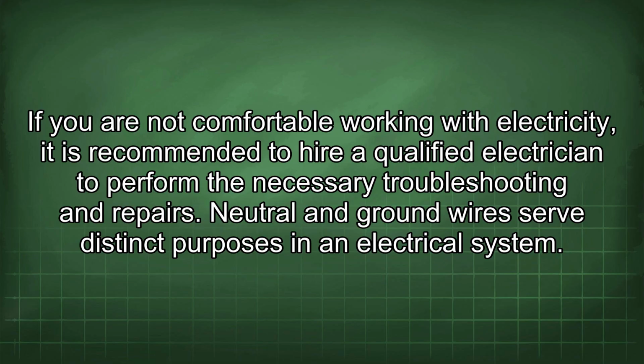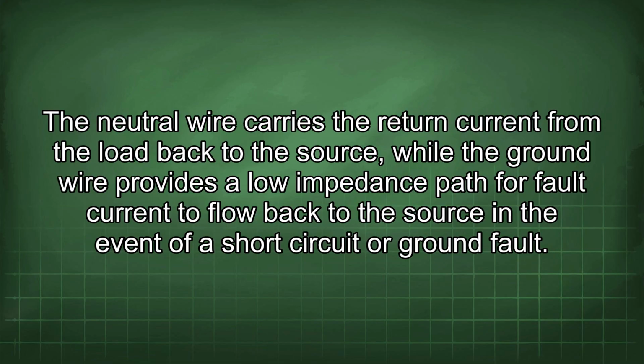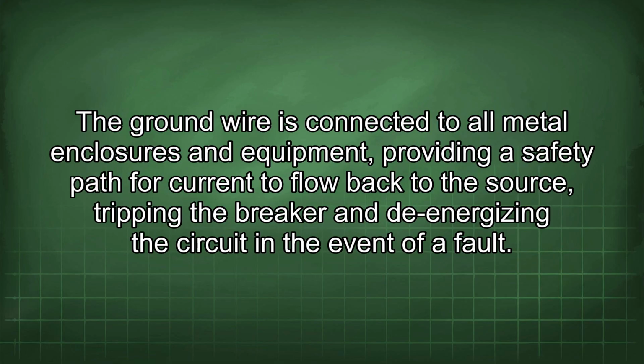If you are not comfortable working with electricity, it is recommended to hire a qualified electrician to perform the necessary troubleshooting and repairs. Neutral and ground wires serve distinct purposes in an electrical system. The neutral wire carries the return current from the load back to the source, while the ground wire provides a low impedance path for fault current to flow back to the source in the event of a short circuit or ground fault. The ground wire is connected to all metal enclosures and equipment, providing a safety path for current to flow back to the source, tripping the breaker and de-energizing the circuit in the event of a fault.